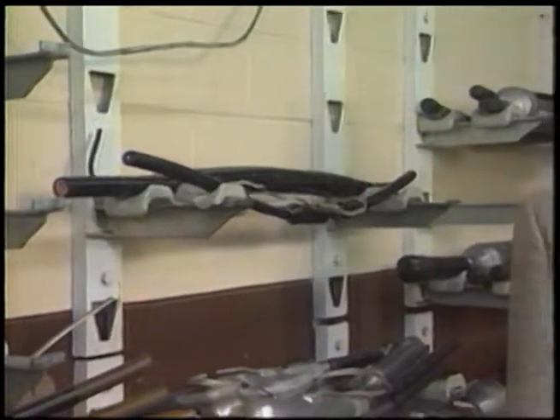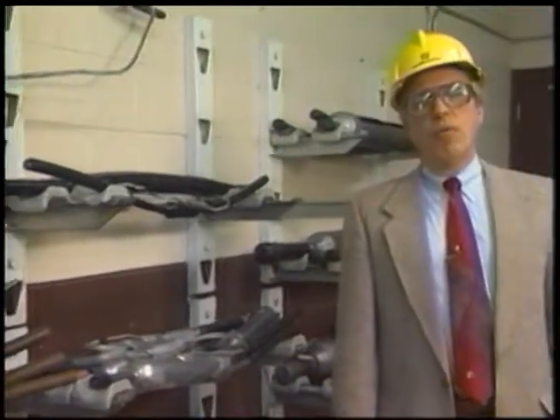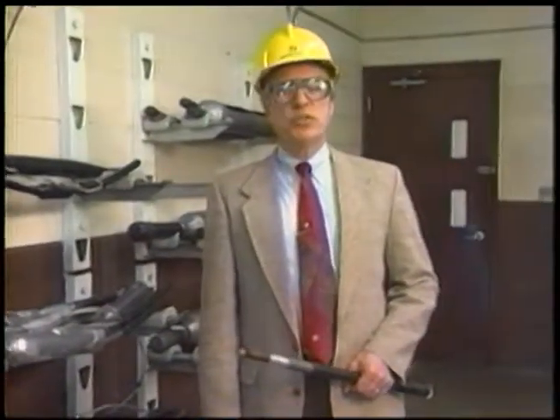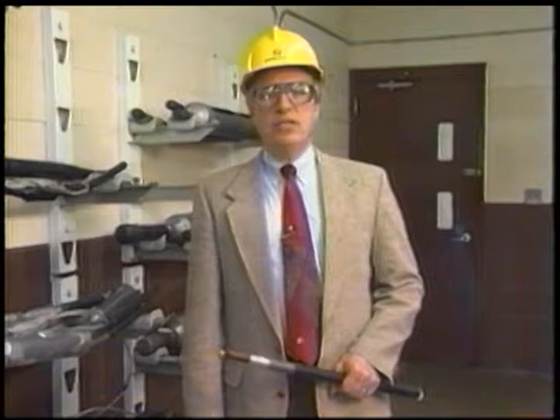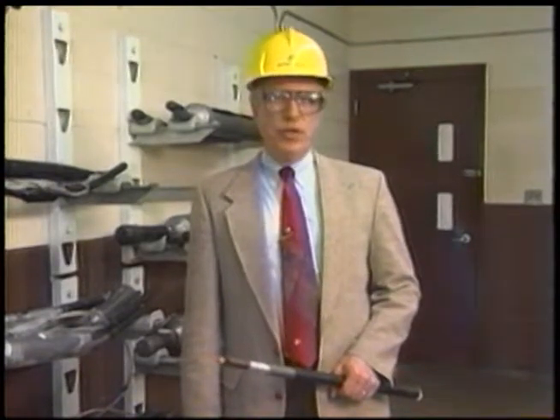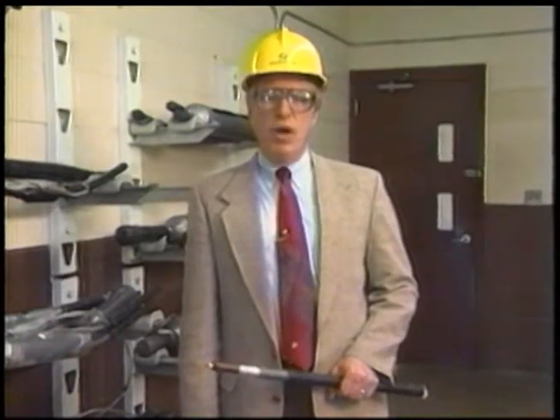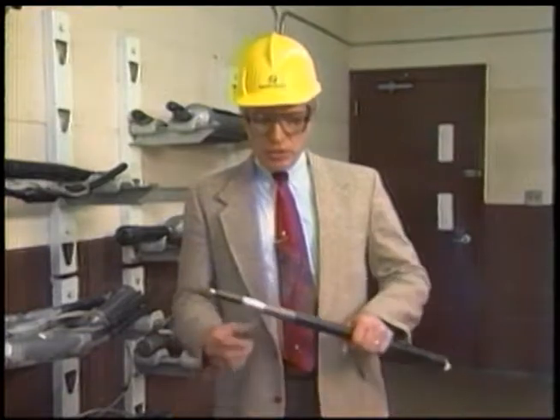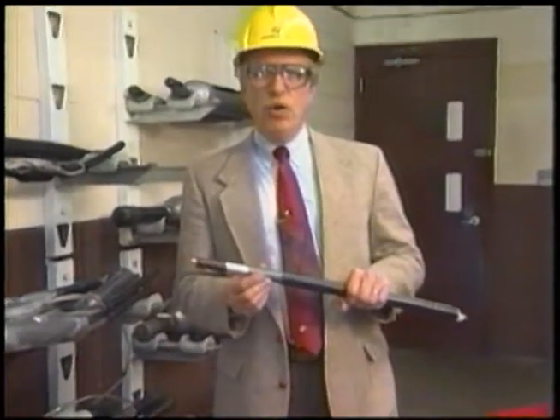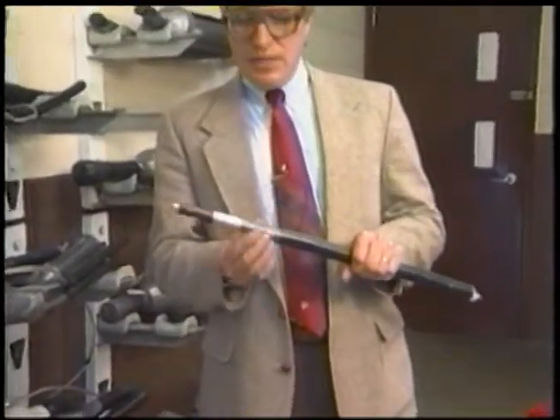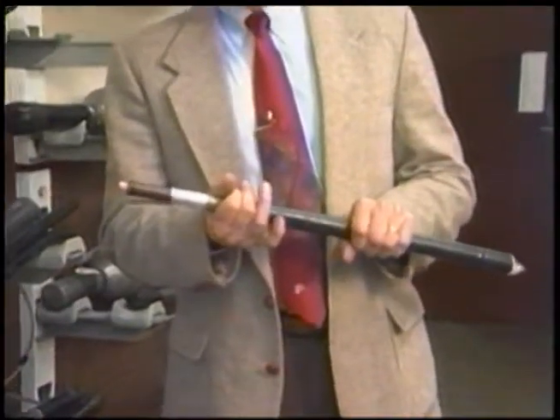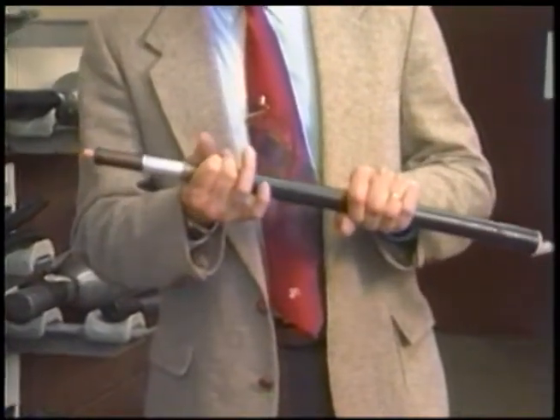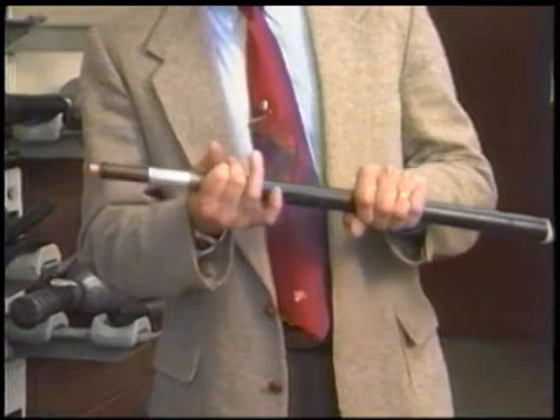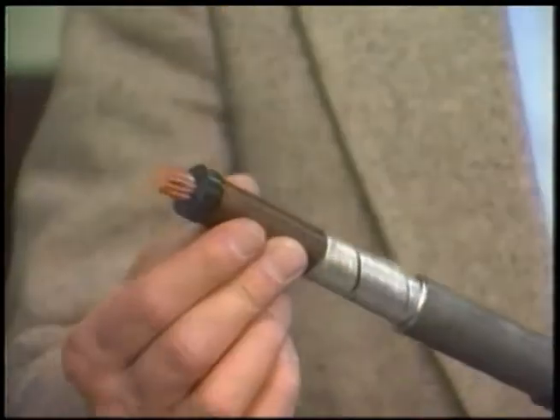Now that you've seen the 3 demonstrations, I want to talk about why it is safe to go into manholes. It's safe to go into manholes without being electrocuted because of grounds and grounding in the manhole. The cable that you saw outside that we set on fire was a paper and lead cable. This is lead that is a ground for the cable, and this now becomes a safety ground for anyone entering the manhole. These are the paper tapes that we set on fire.